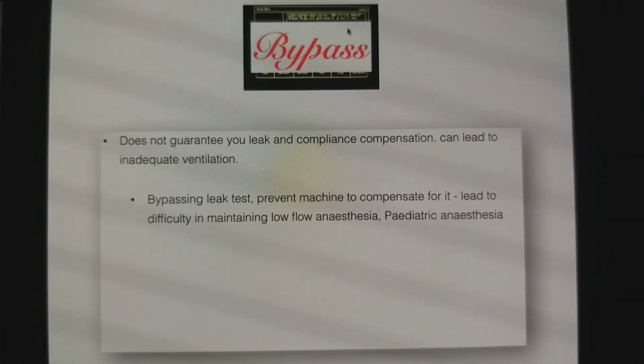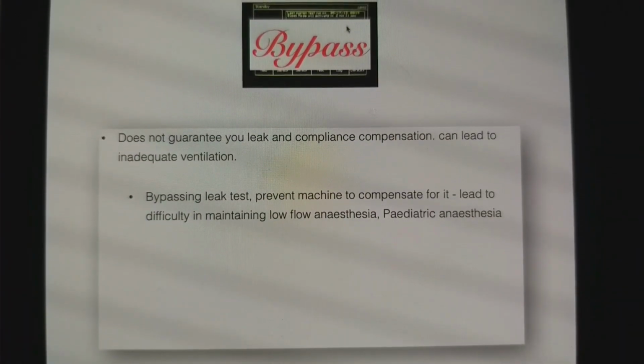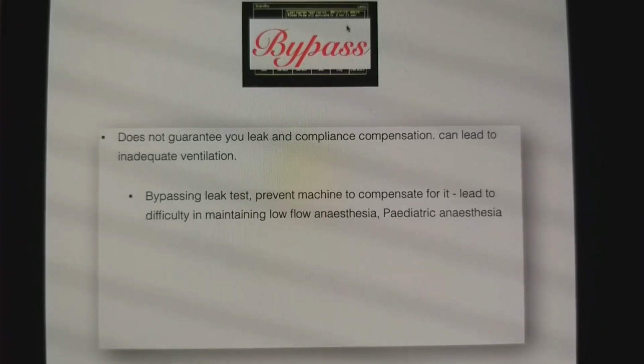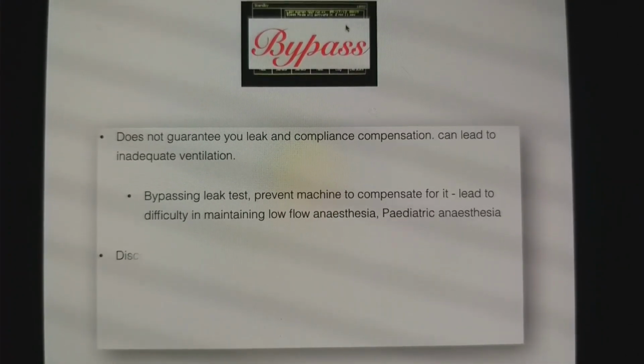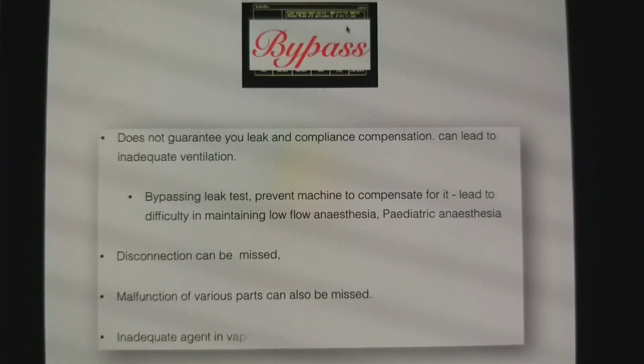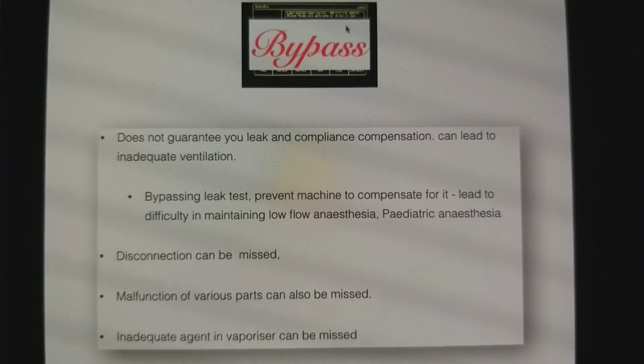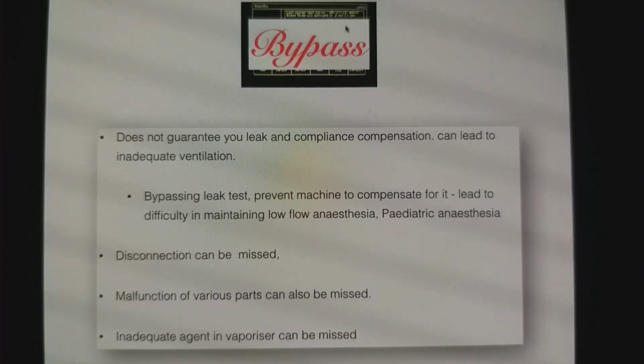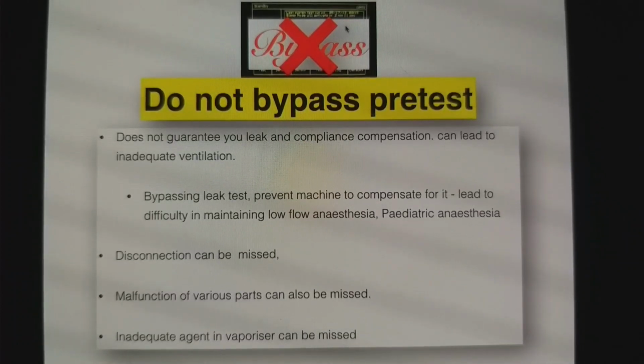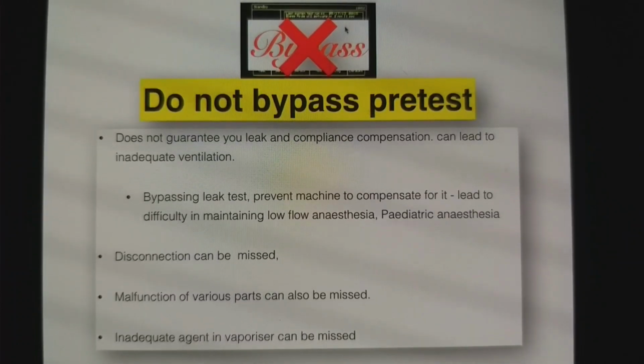Our problem is that we tend to bypass it. We are in a hurry, we don't know the importance of it, and we tend to bypass it. Even if it is actually giving us a leak, we tend to bypass it and start the anesthesia work. It then does not compensate for the leak as well as the compliance. Also, you will miss a lot of disconnections, malfunctions, or sometimes inadequate agent available. So never bypass your pre-test. As far as possible, always do it.